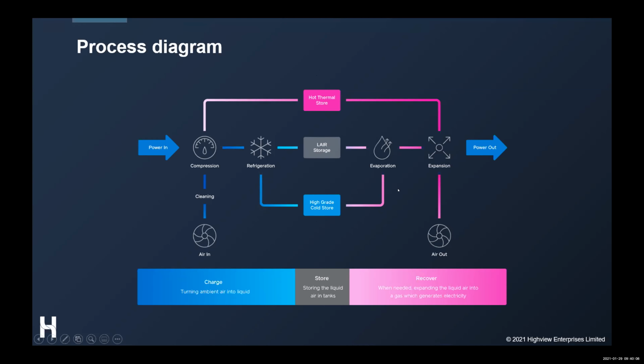On the discharge side, we have our power recovery system. We pump up our liquid air in a multi-stage centrifugal pump, or a number of them, to about 150 bar. We turn the liquid into a gas by running it across a heat exchanger, which we call an evaporator. This should probably be called vaporization more than anything else. But as it heats from minus 150 to about 20 degrees Celsius, we take off that valuable cold sensible energy, and that's what's stored in our low temperature thermal sink. We continue to reintroduce heat into our gas, and we run it across a 4-stage axial steam derivative turbine, and we produce mechanical power, which is sent to a generator to send electrical power to the grid.